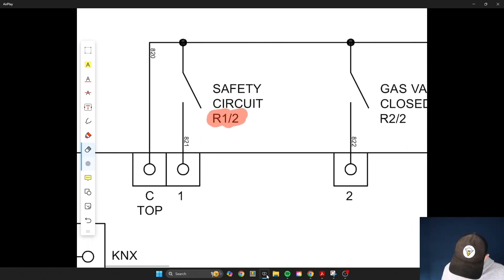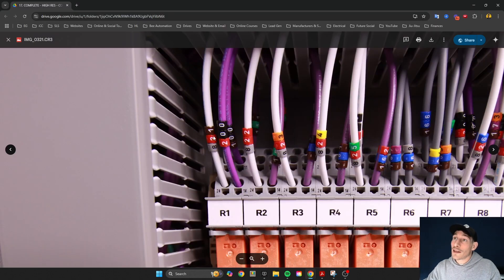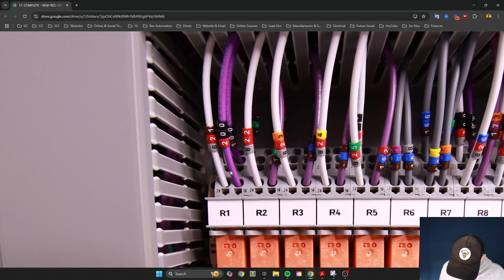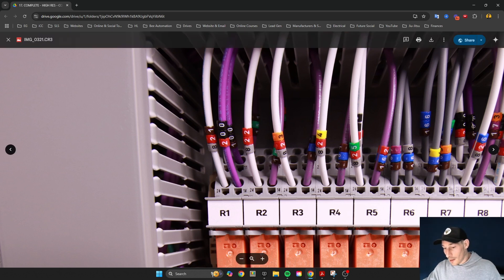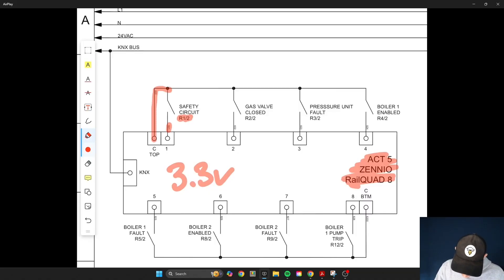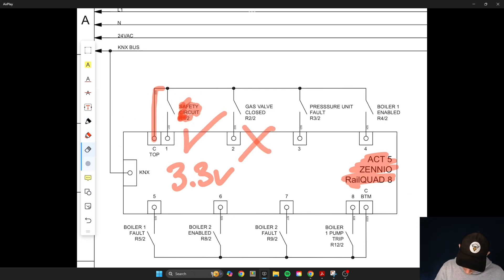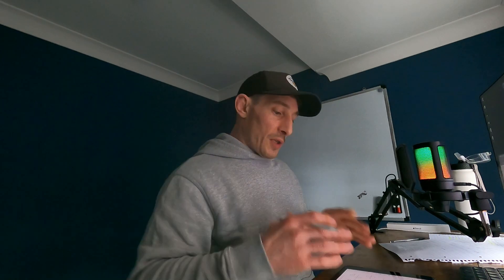The second pole of this relay is over on this page, feeding the PLC control module. You can see right here R1/2 — the second pole — labeled 821. When that coil energizes, the same operation happens on both poles simultaneously, but they're galvanically isolated. We want that because this PLC module outputs 3.3 volts while the other side is 24 volts AC. The PLC knows when there's a safety circuit failure because that contact will open or close, feeding a signal into the PLC.